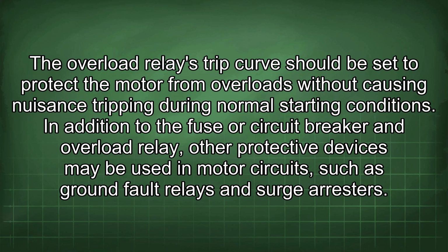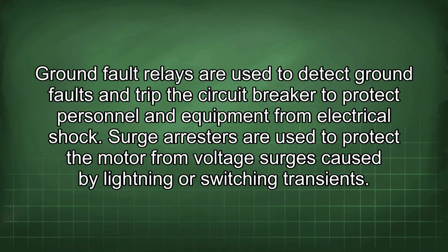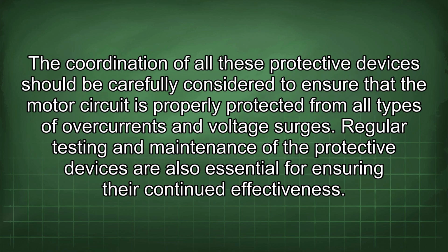In addition to the fuse or circuit breaker and overload relay, other protective devices may be used in motor circuits, such as ground fault relays and surge arresters. Ground fault relays are used to detect ground faults and trip the circuit breaker to protect personnel and equipment from electrical shock. Surge arresters are used to protect the motor from voltage surges caused by lightning or switching transients. The coordination of all these protective devices should be carefully considered to ensure that the motor circuit is properly protected from all types of overcurrents and voltage surges.